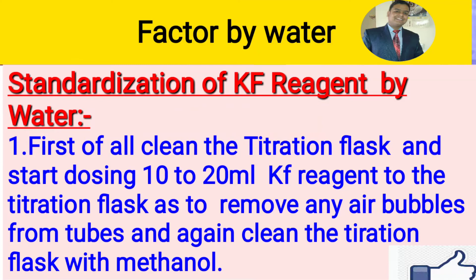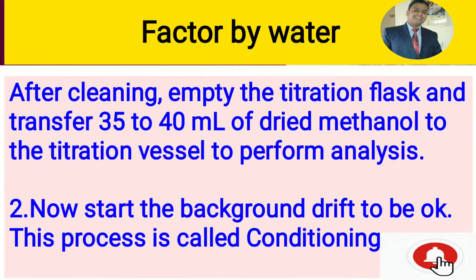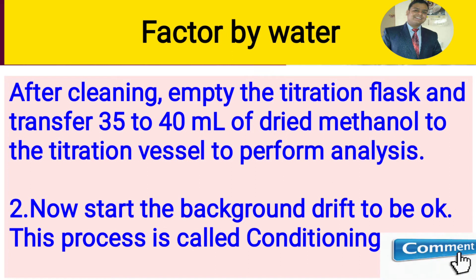For factor by water: first, clean the titration flask with dried methanol, then start dosing 10 to 20 ml of Karl Fischer reagent into the titration flask to remove any air bubbles present in the tubes. Then dispense this KF reagent and again clean the titration flask with dried methanol. Now take 35 to 40 ml of dried methanol in the titration flask and start the background drift. This process is called conditioning — it removes background moisture present in the titration flask.